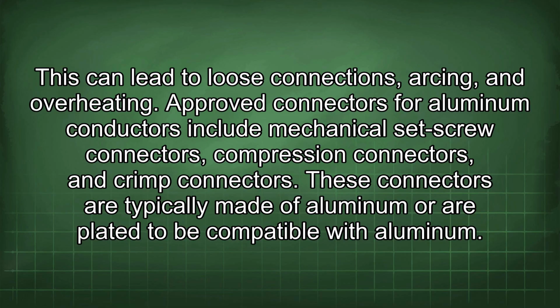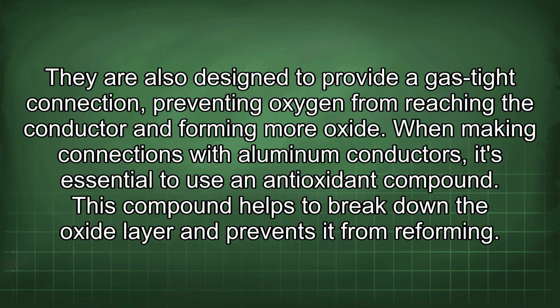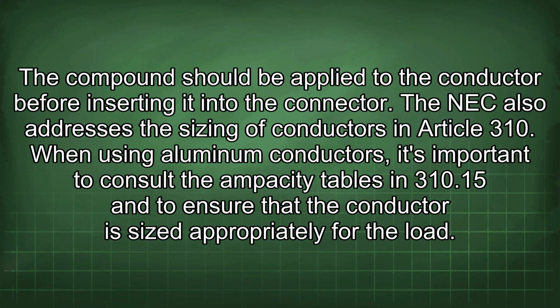Approved connectors for aluminum conductors include mechanical set screw connectors, compression connectors, and crimp connectors. These connectors are typically made of aluminum or are plated to be compatible with aluminum. They are also designed to provide a gas-tight connection, preventing oxygen from reaching the conductor and forming more oxide. When making connections with aluminum conductors, it's essential to use an antioxidant compound. This compound helps to break down the oxide layer and prevents it from reforming. The compound should be applied to the conductor before inserting it into the connector.